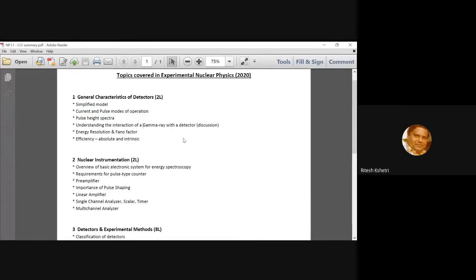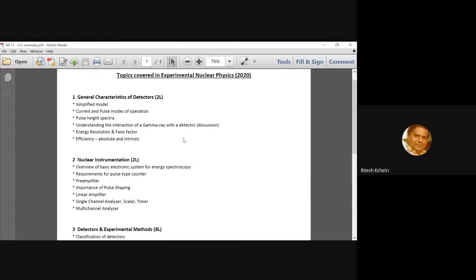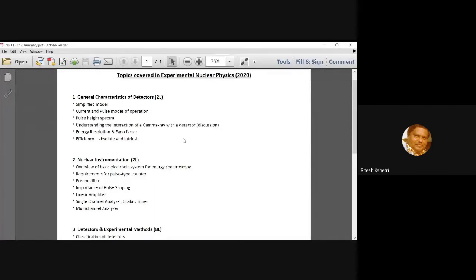I talked about the peak, overshoot, undershoot and how do the signal, how do you see them as they come out of the pre-amplifier and then afterwards from the amplifier. How does the signal look like? We talked about them. And then afterwards there was a discussion on the discriminators, two very important discriminators, the single channel analyzer and the multichannel analyzer. Okay.